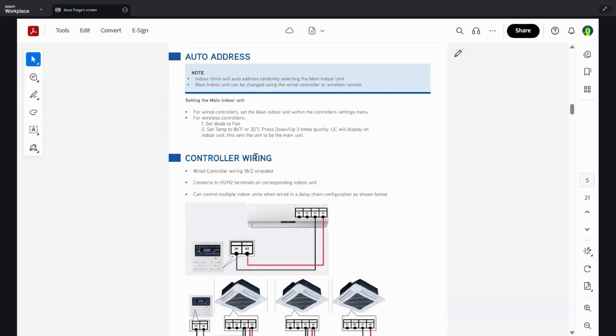And so here's more information on how to do that. You set the mode to fan, set temperature 86 or 30 degrees Celsius, and press up and down 3 times quickly. UC will display on the indoor unit. This sets the unit to be the main unit. This applies to wireless controllers.